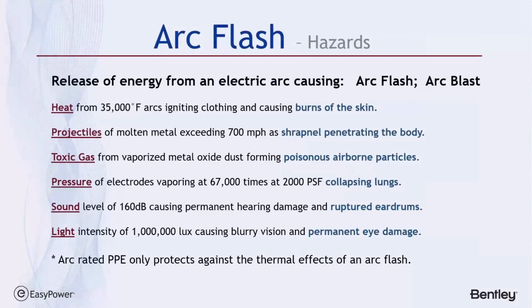So during the testing, the definition of an arc really gives us a summary of these types of hazards that could be produced. There's usually a large amount of heat, in some cases in a worst case situation, greater than 35,000 degrees Fahrenheit, which exceeds the surface temperature of the sun. There's a potential for molten metal projectiles, potentially toxic gas from vaporized metal oxide or insulation that's been vaporized. There often is a pressure wave because the arc will cause the air to expand multiple times its volume, as well as the vaporization of the metal involved.